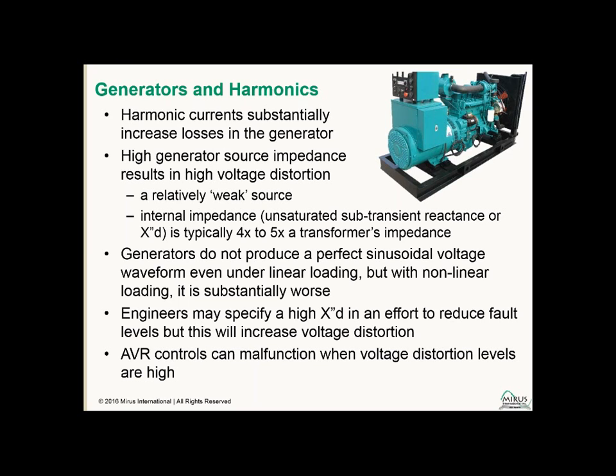The generator's high source impedance makes it a weak source. As a weak source, it will introduce much higher levels of voltage distortion. The internal impedance of a generator is typically 4 to 5 times that of an equivalent size transformer's impedance. So if you're loading the generator at the same level with a nonlinear load that you would be loading a transformer, you're going to have 4 to 5 times the level of voltage distortion on the generator. Generators, even when they're supplying a linear load, do not produce a perfectly sinusoidal voltage waveform, but when there are nonlinear loads, the extra distortion is quite high, and there are significant increases in that level.